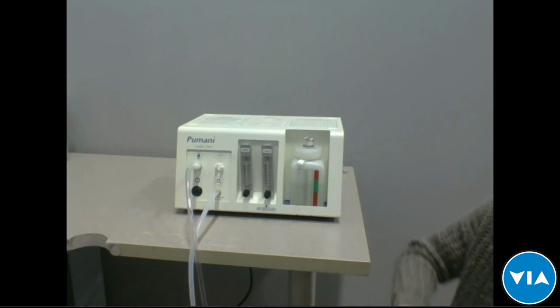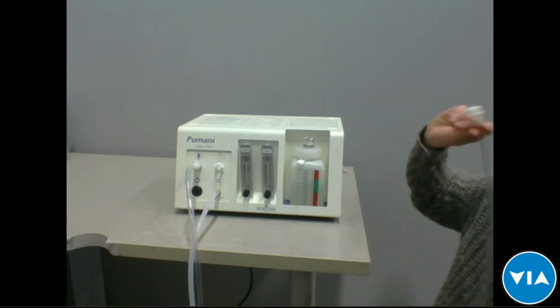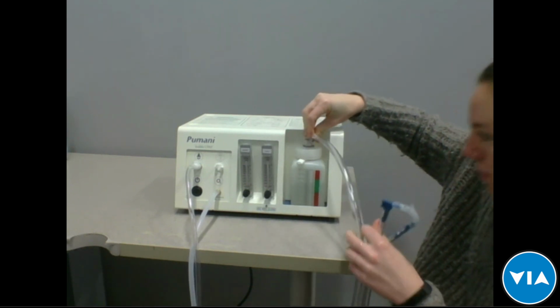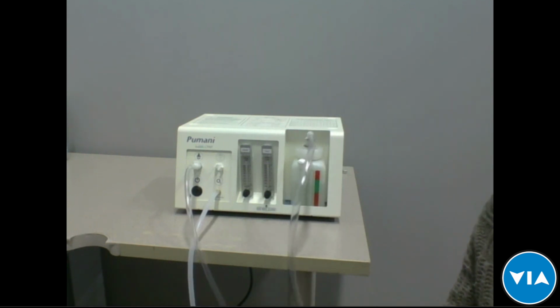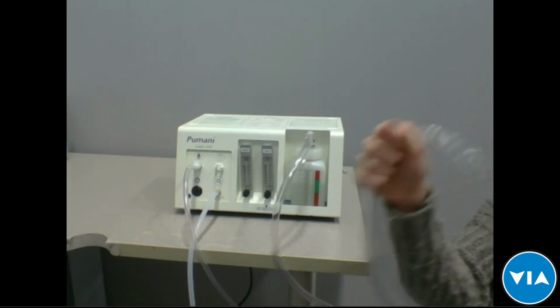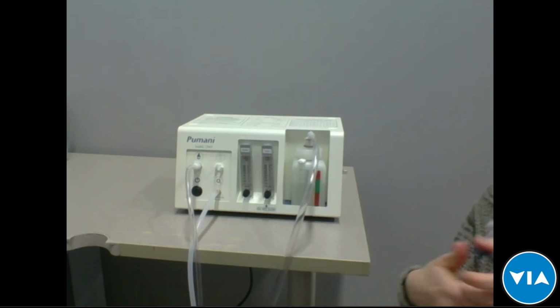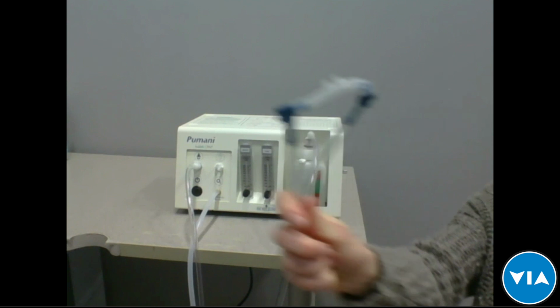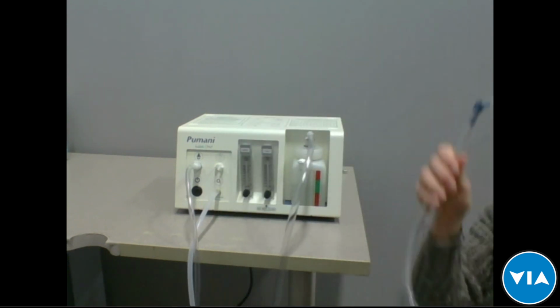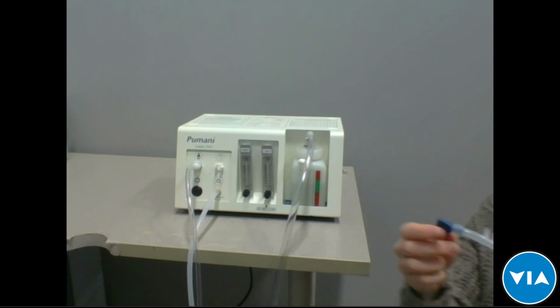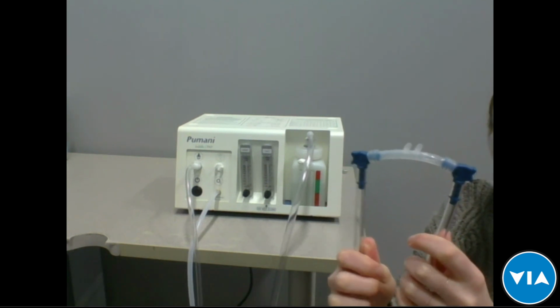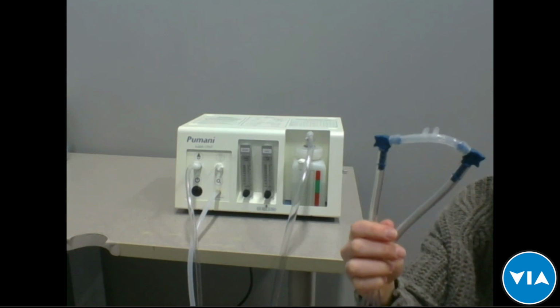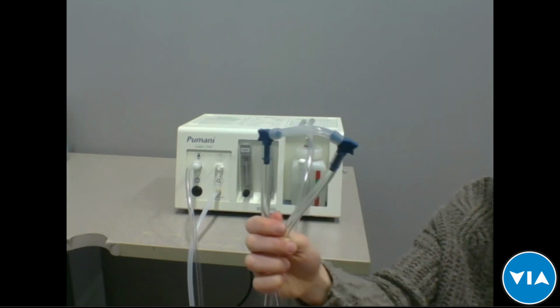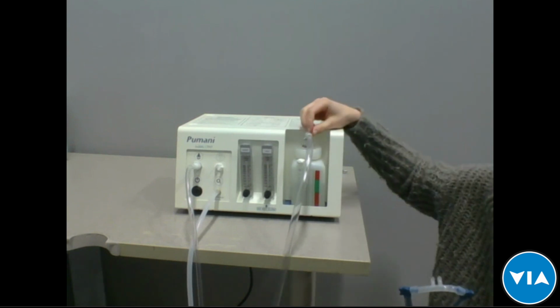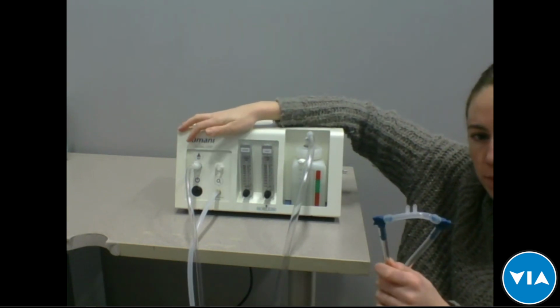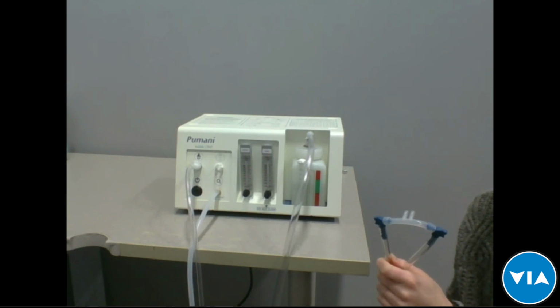And then we have the expiratory tubing, which also snaps in only in one direction into the bottle. And that's where the blended air and oxygen pass out, expired out of the baby and into the bubbler, which then creates the actual pressure, the PEEP. So once you have those connected, you connect the prongs and the fish elbows to that tubing, depending on the size you've selected. And your entire circuit is complete. So you can look at the prongs, the inspiratory tubing, the expiratory tubing, and the fish elbows all together.